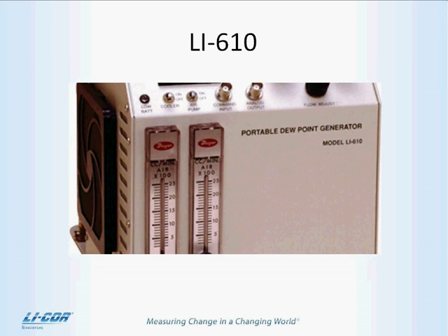So you would want to make sure that one was on battery and one was on AC power if you did. The other thing is you'll have to make some chemical column changes. You'll have to put your chemical columns, for example, your soda lime, before the 610, not after, because otherwise the flow rates change and you end up adding CO2 and things like that. So you do have to make some chemical column changes.